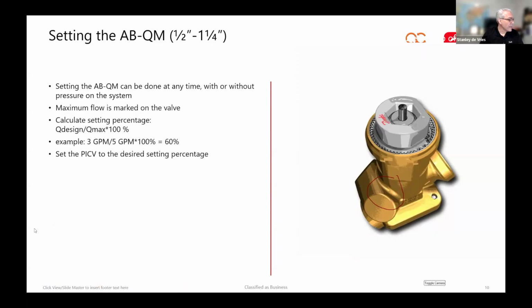That is a very simple way, and it's also how the whole range works. There's a percentage scale on the valves, you calculate the percentage, and then you set it to that. So now finally it wants to do its job. This is how you do that on the small setting. For the bigger valves, you need a spanner to do it. But for the small ones, up to 1 1/4 inch, you can just use your hand.